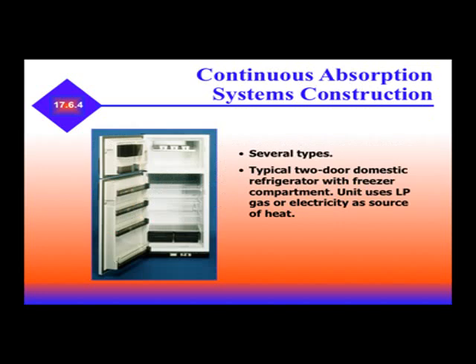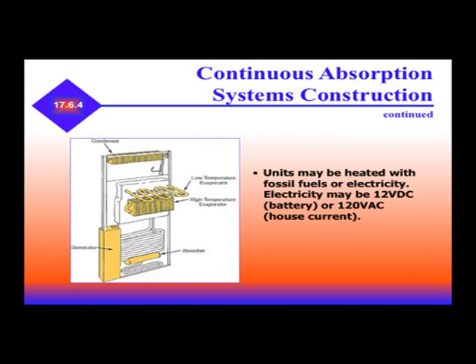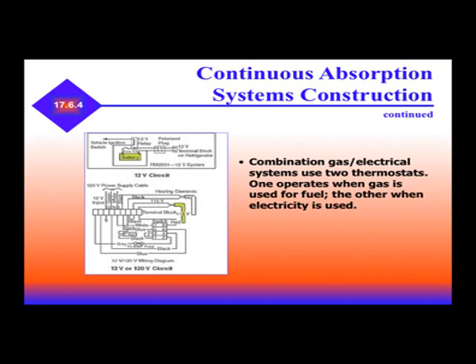For continuous absorption system construction, there are several types. A typical two-door domestic freezer uses LP gas or electricity as a heat source. Units can be heated with fossil fuels or electricity — electricity may be 12 volts DC or 120 volts AC. A switch is used to change over from DC to AC. Combination gas-electric systems use two thermostats: one operates when gas is used for fuel, the other when electricity is used.